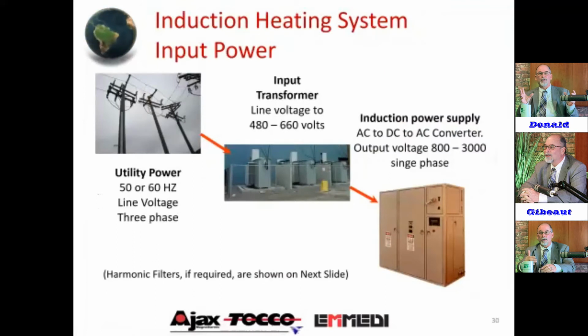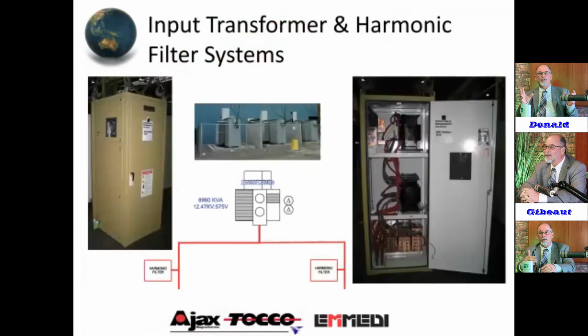So the line makeup, as we showed you going through the line, we bring in line utility power. 12,470 is more common here in North America, and then we step it down to 480 or 660 volts. Then we deliver it across our AC to DC to AC converters, our power supplies, as we call them, that's pulsed to semiconductor devices. Here is a harmonic filter. We have a company called Control Transformer that makes our reactors, and we make our own harmonic filters that we bolt onto our power supplies that filter out the targeted harmonics outputted out of the induction, which typically we're focused on the 5th, 7th, 11th, and 13th harmonics. This compensates for your high power demand power supplies.